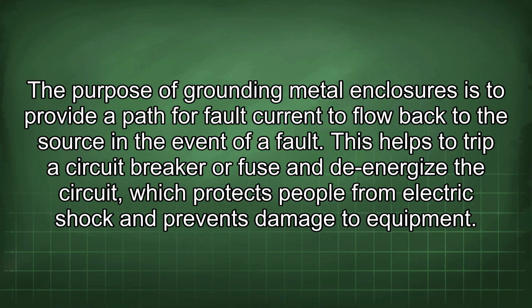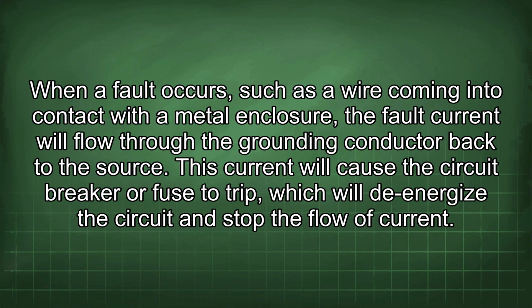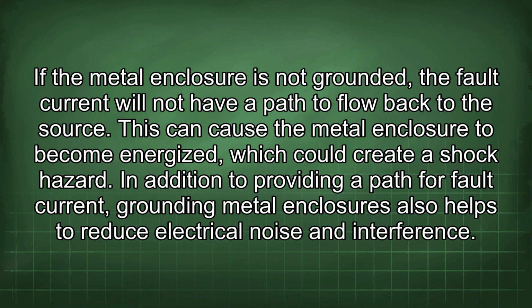This helps to trip a circuit breaker or fuse and de-energize the circuit, which protects people from electric shock and prevents damage to equipment. When a fault occurs, such as a wire coming into contact with a metal enclosure, the fault current will flow through the grounding conductor back to the source. This current will cause the circuit breaker or fuse to trip, which will de-energize the circuit and stop the flow of current. If the metal enclosure is not grounded, the fault current will not have a path to flow back to the source. This can cause the metal enclosure to become energized, which could create a shock hazard.